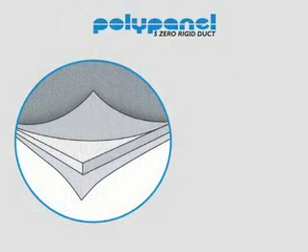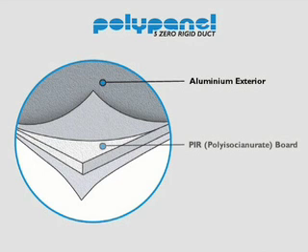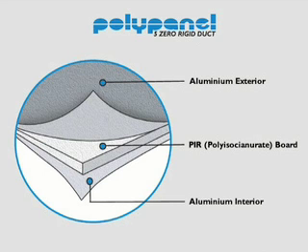Polypanel is closed-cell polyisocyanurate foam enclosed in 2 layers of textured aluminium sheet. The embossed aluminium sheet creates a sturdy exterior which protects from impact, and a clear lacquer coating increases corrosion resistance. The PIR foam is light and a good insulator.